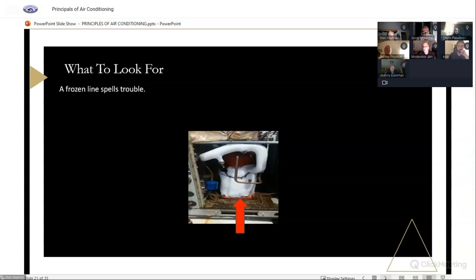Check your return air filter first. If that thing is plugged solid, this is the result. We had a situation, Stan, a couple of weeks ago. I showed up to an inspection and it was frosted over, but I quickly saw that a branch had prevented the fan from spinning. So I removed that, and within like half hour, it was functioning fine, and the frost had melted. Yeah, so every component in the system has to be working for it to work properly. Anything that's not working or not working at 100%, dirty, it's not good. It's a very simple process, but all the stars have to align.